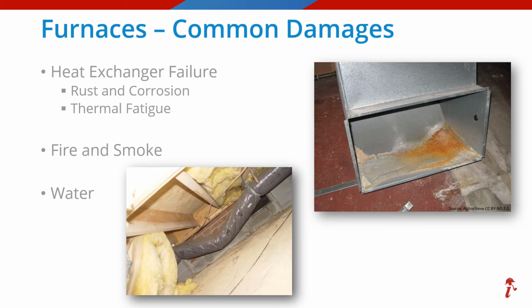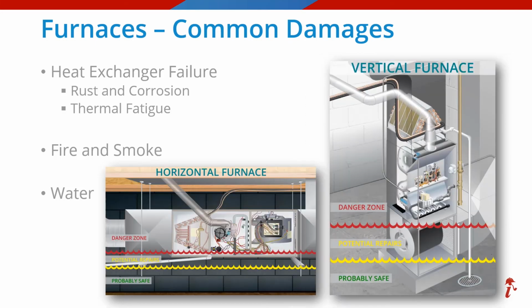And regarding water losses, don't forget that you will need to consider other factors such as how much water, how long was the unit wet, the type of the water, and the overall condition of the unit before the water loss. Many times we may be able to dry and clean the furnace and or metal ductwork and replace just the electrical components affected and the flex duct. These graphics of both a vertical and horizontal furnace might help you visualize how much water it might take before the unit is at true risks of catastrophic damages. Notice water can get to those sensitive components a lot faster with horizontal units just based on its orientation and the location of the internal components. Don't forget the water could also come from above in an overhead water loss scenario.